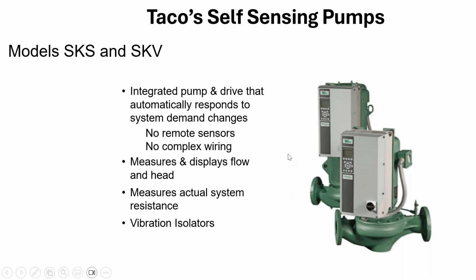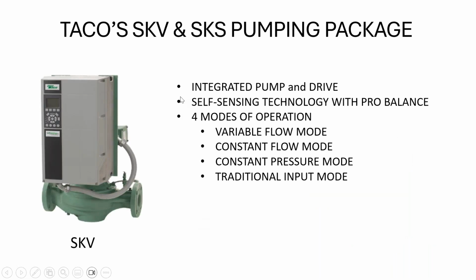One thing that we have done, and the R&D engineer actually just retired, Steve Sullivan, the TACO gentleman, good for him. I hope he enjoys his retirement. He was a little worried about vibration on these drives. So it's hard to see right here, but there's 4 vibration isolators where the drive mounts to that bar that's in the back there. And in the testing that we did, we're well below the requirements set forth by Danfoss. And then the system balancing. This is the do-it-yourself system balancing with self-sensing Pro Balance, and I'm going to show you that a little further in the project. So, and again, integrated pump and drive.